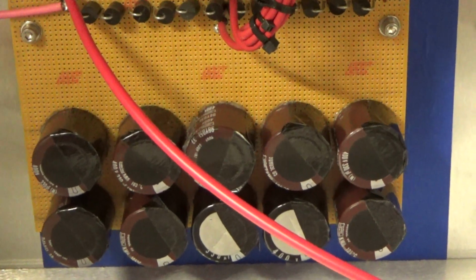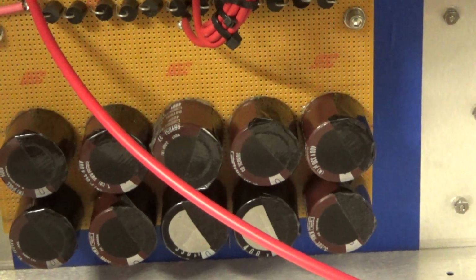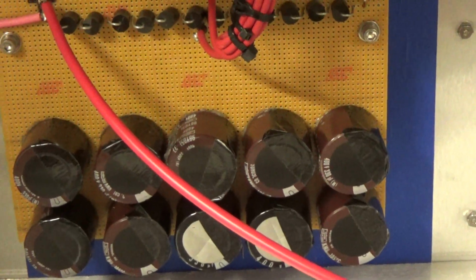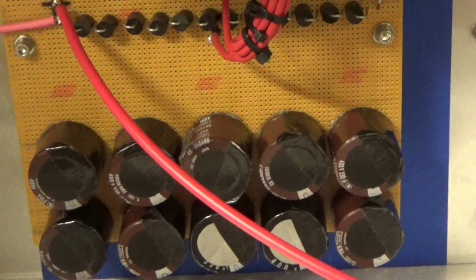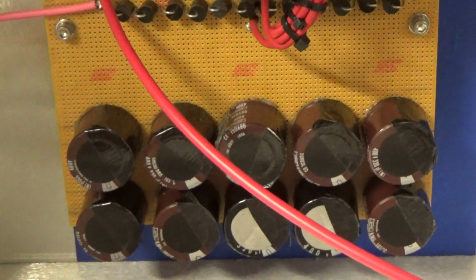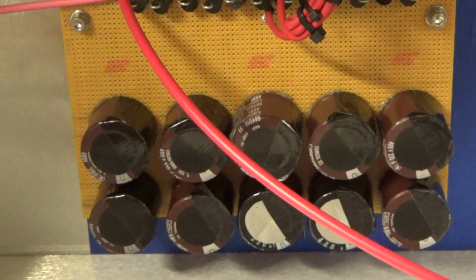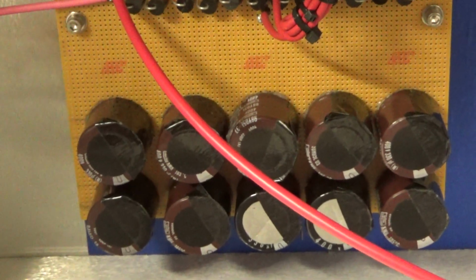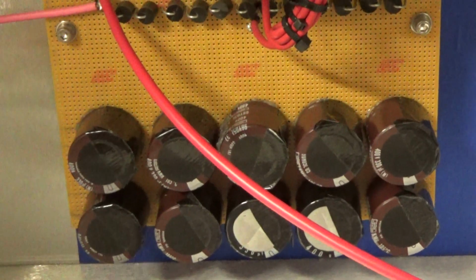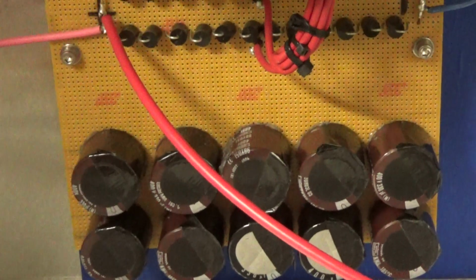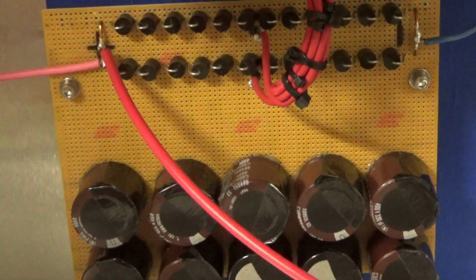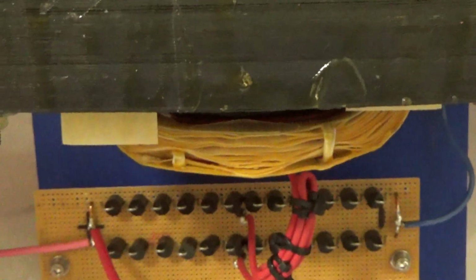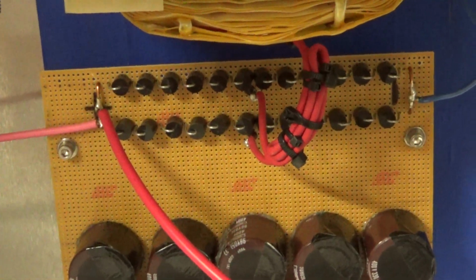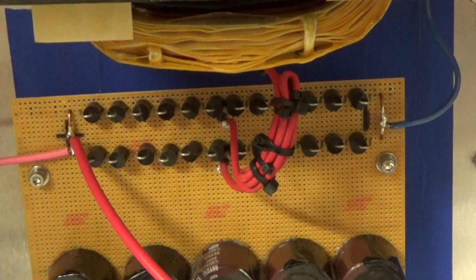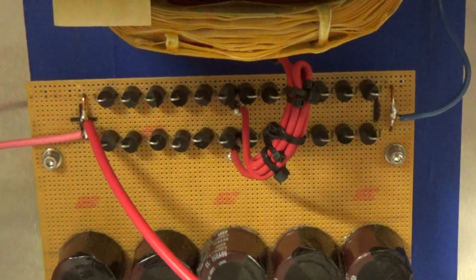So to figure out the amount of volts per primary volt, you take 2650 divided by the primary voltage, which is what the transformer is wound for. What it says on the transformer: 240.